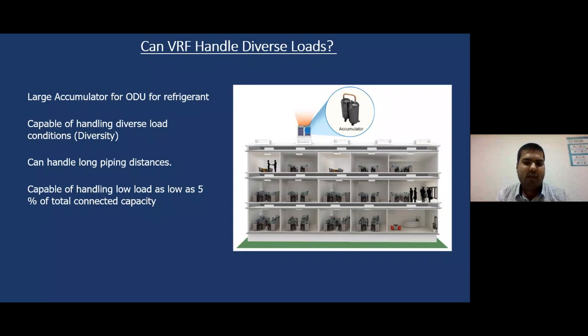There is always a possibility that all my machines would not be running all the time. So why should I pay the initial cost of 6 tons of AC when my requirement is only 4.5 tons most of the time? Diversity is always considered depending on the application, whether it's a hospital, a hotel, or a house. So diversity changes for other conditions as well. VRF can also handle long piping distances, and can handle loads as low as 5% of total connected capacity.